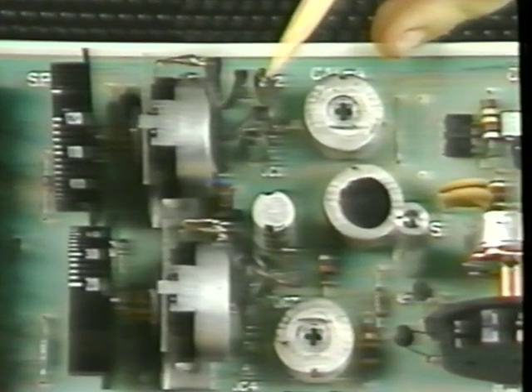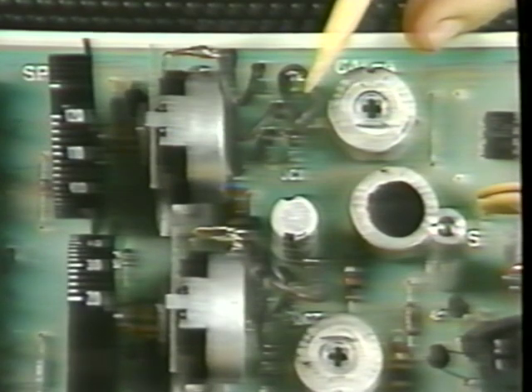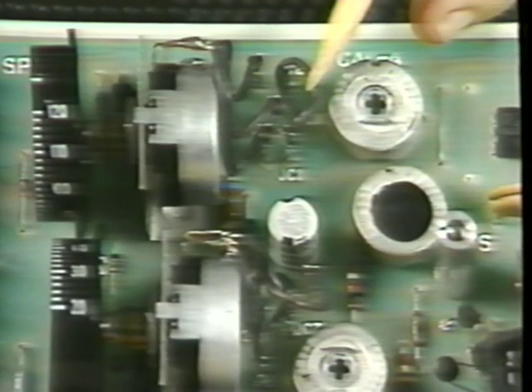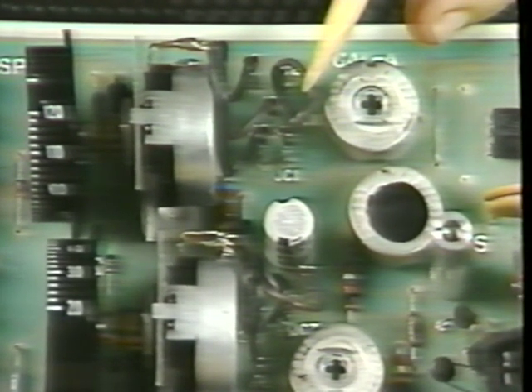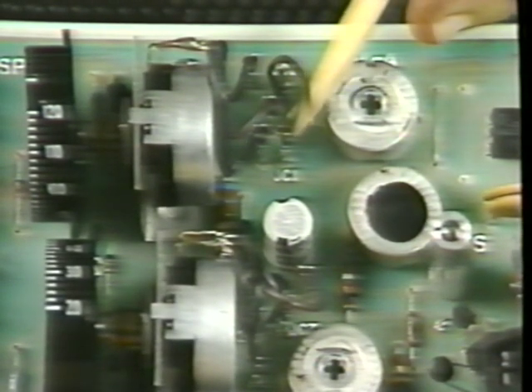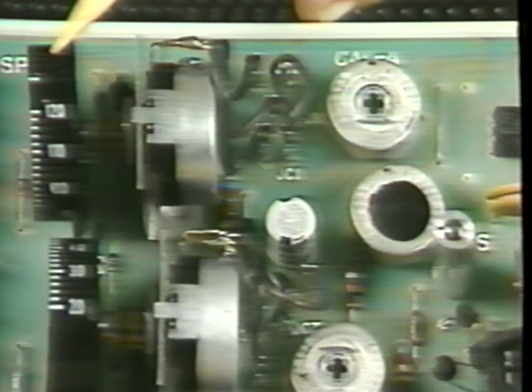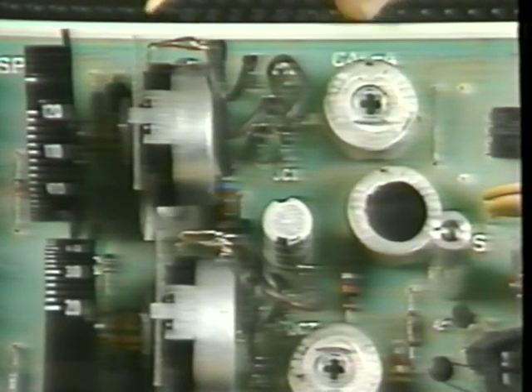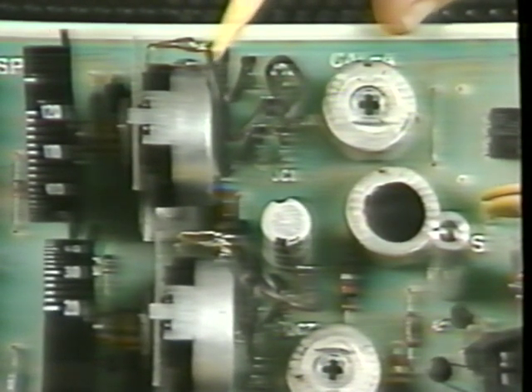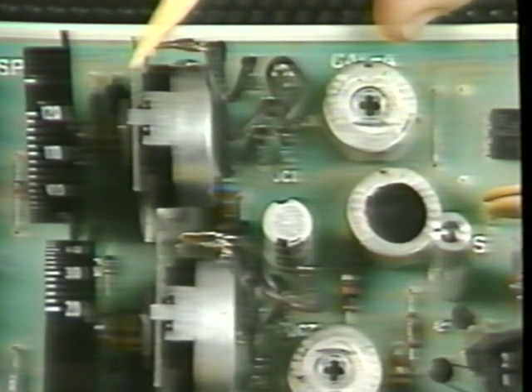Set point A jumpers. There are 2 jumpers associated with set point A. The first one, the brown one shown here, is jumper J1. This permits disabling of set point A while keeping bridge A intact. By moving this jumper from its factory position, J1 to pin JC1, over to pin JC2, the set point adjuster itself is bypassed. If desired, bridge A can also be disabled by removing the center tap wire from the set point pot from its pin, which is marked A.